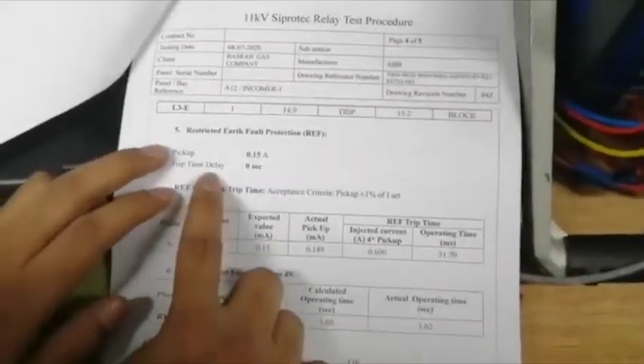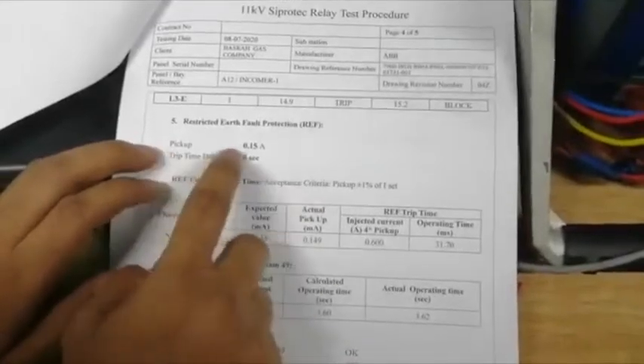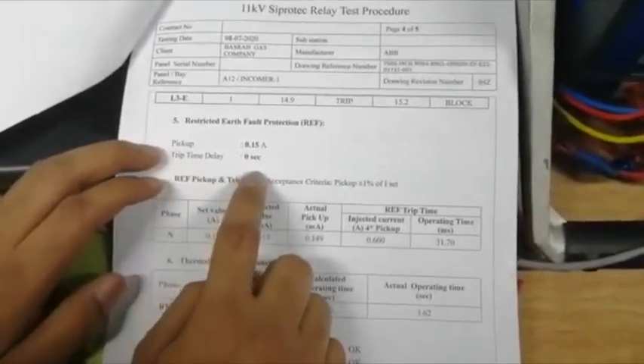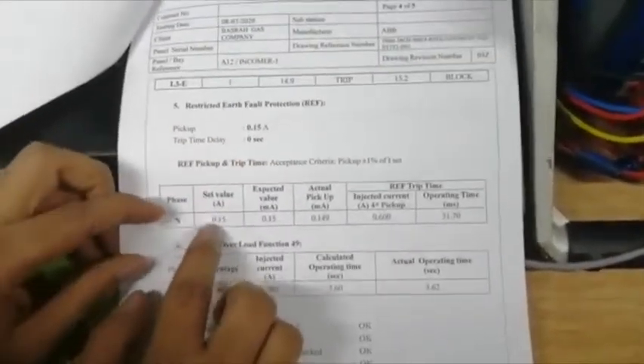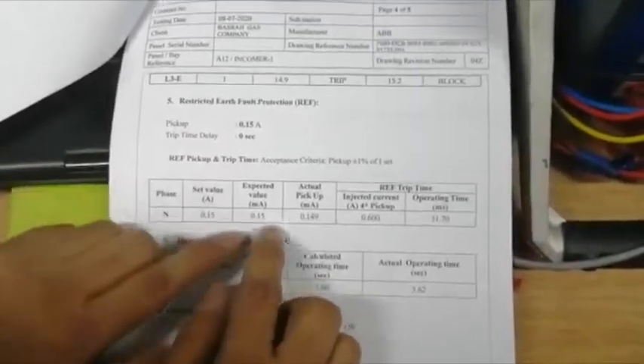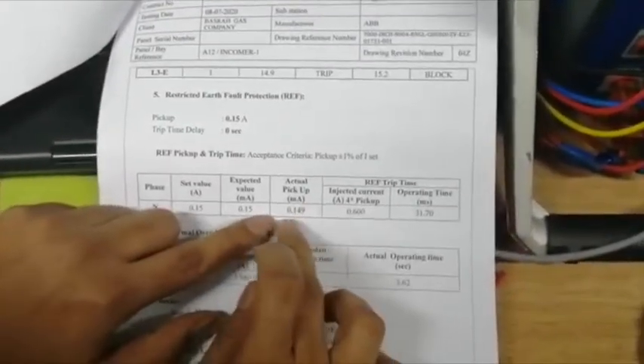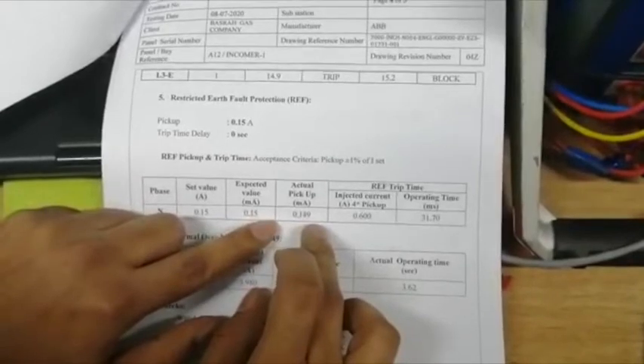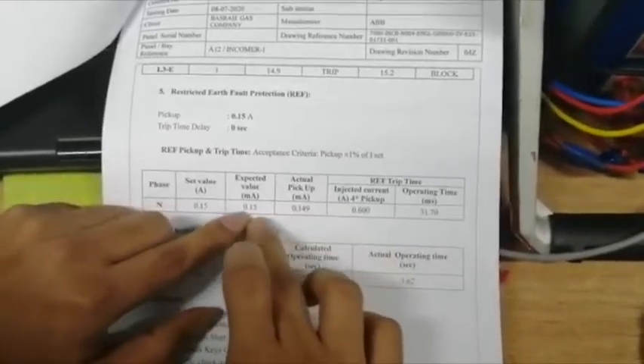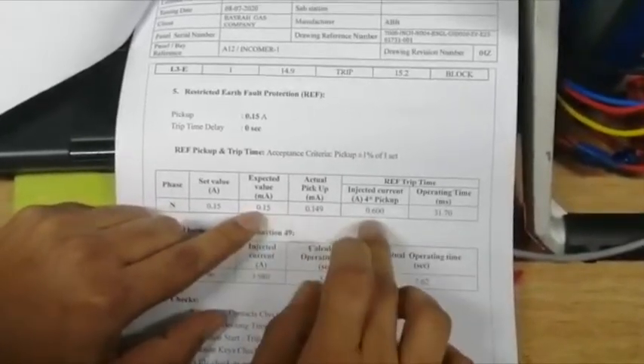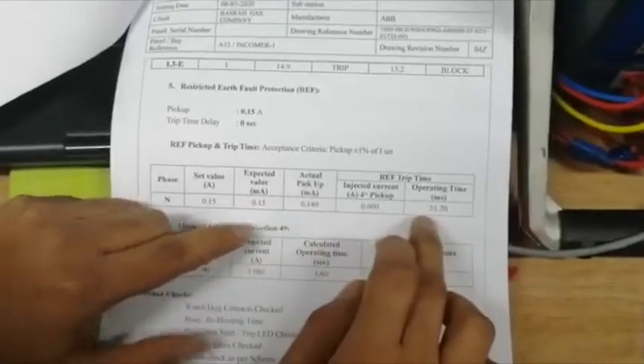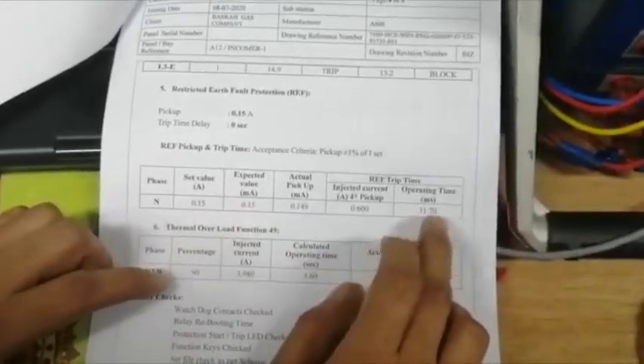Next, restricted earth fault protection. Our setting is 0.15 and 0 seconds trip time. Set value 0.15, expected value 0.15 only. Actual pickup value 0.149. And 4 times of this expected value 0.6. For this, I got 31.70 milliseconds as a trip time.